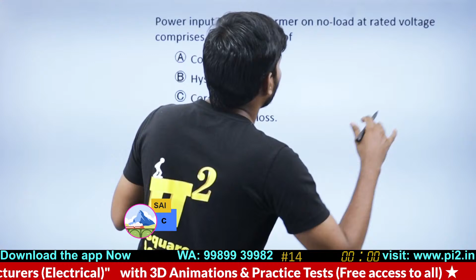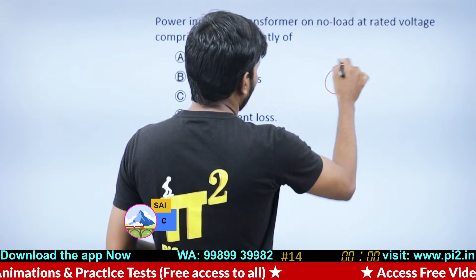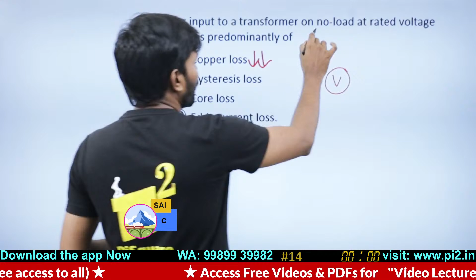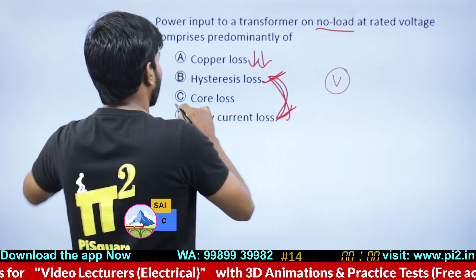Come on guys, power input to a transformer on no load at rated voltage. Rated voltage is there, no load condition is there. Copper losses will be very less because it's on no load. Eddy current and hysteresis losses will be present. The predominant loss is the sum of these two, which is the core loss. Core loss is the predominant case here.